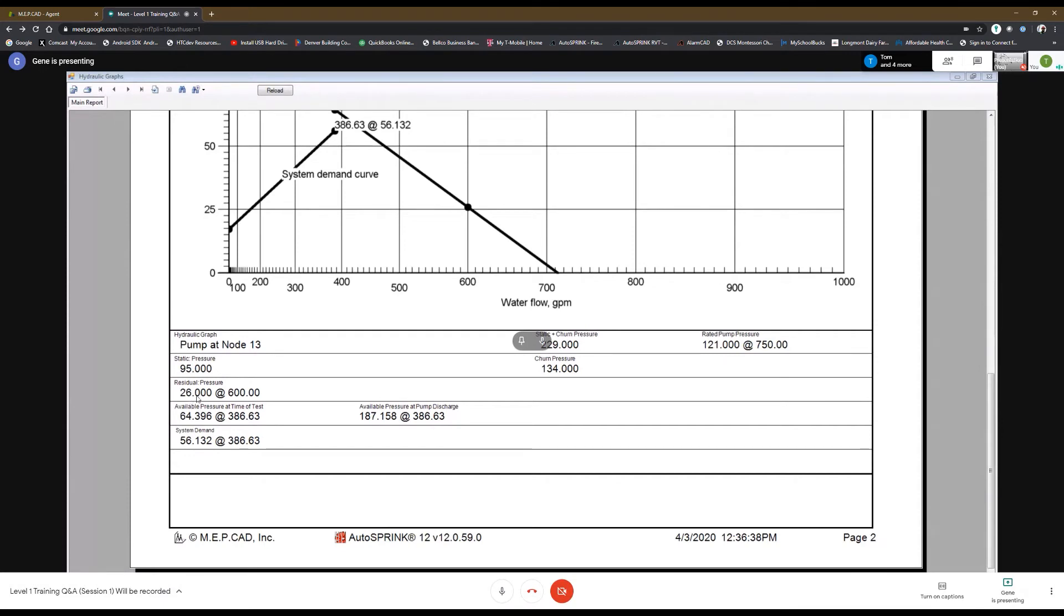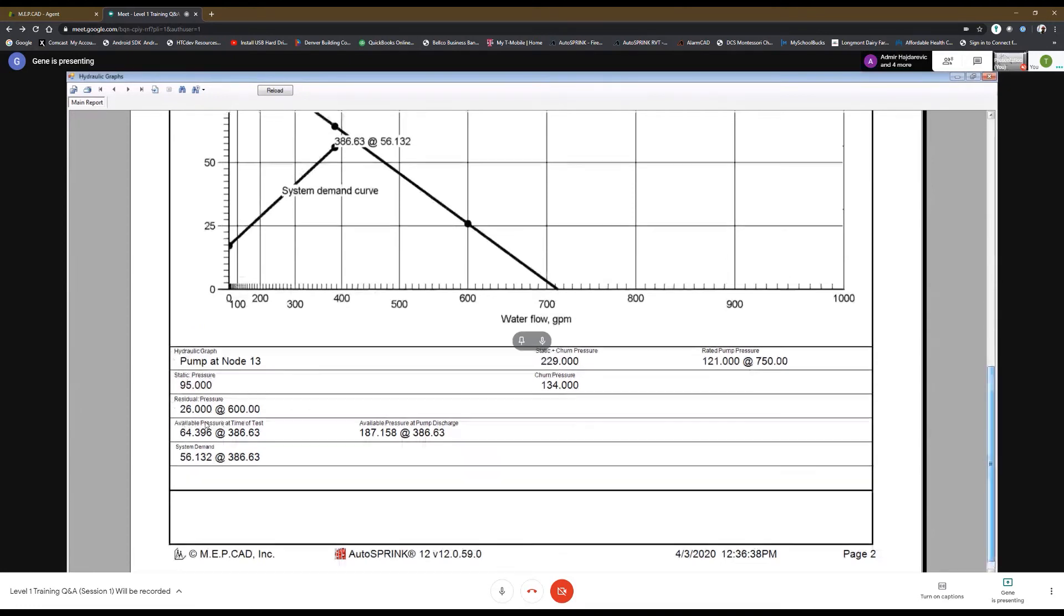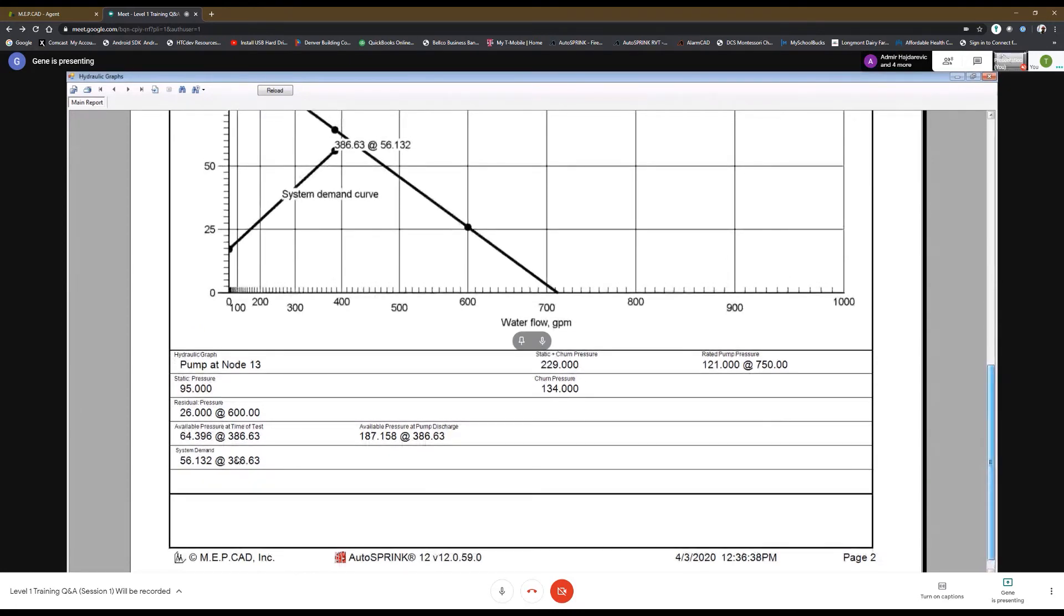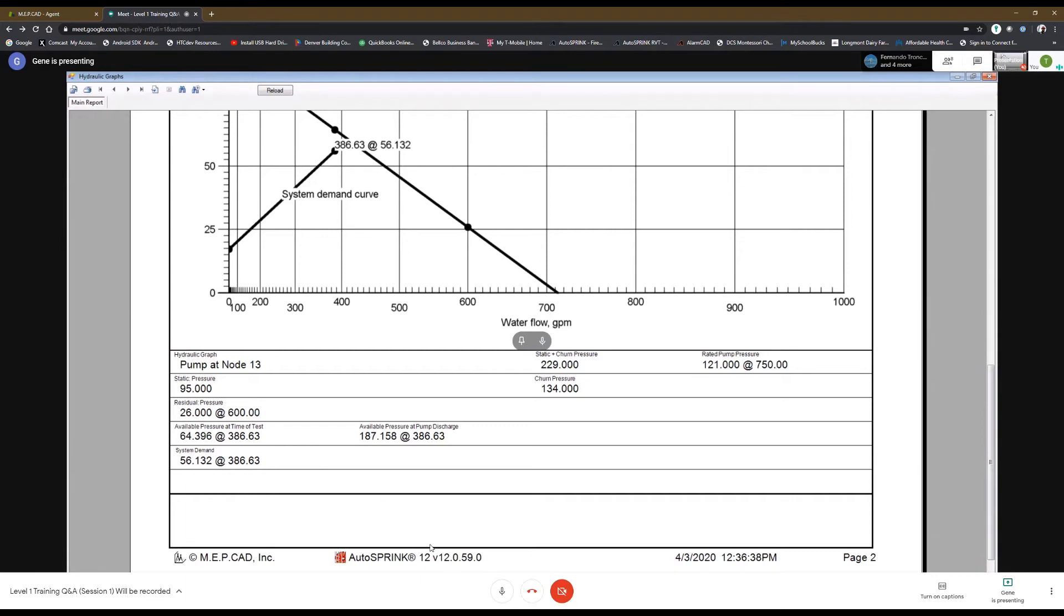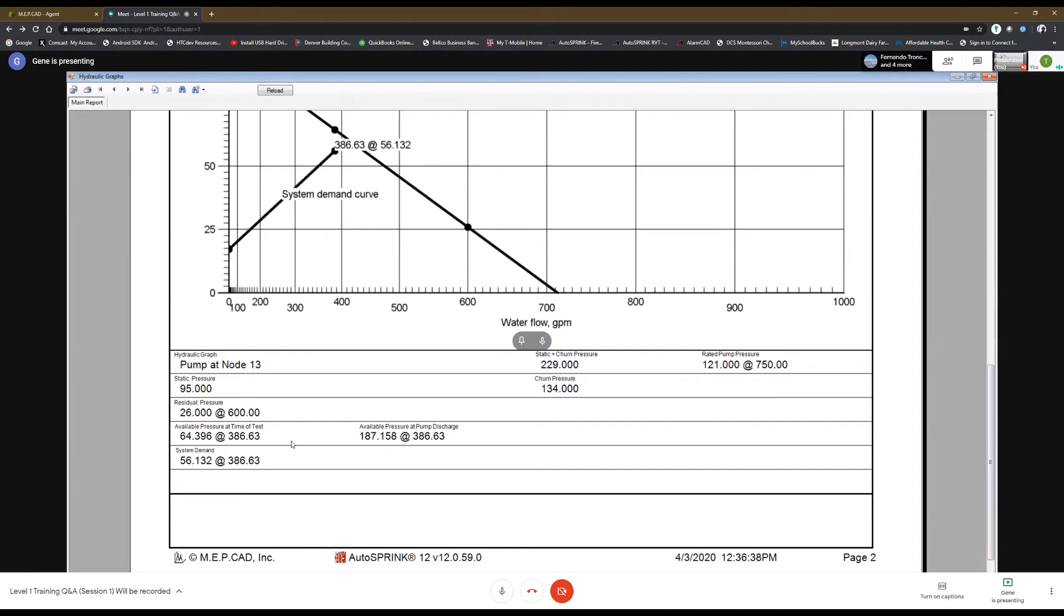Yes, sir. So, there's a bit of a safety factor at the fire pump here. So, the program is basically saying that you've got 64 PSI available at the fire pump, and your system requires 56 PSI at the fire pump. This is an older version of Autosprink. This is, you're on 12. Yeah, it's 12. I believe in 2019, and I could be wrong, but I feel like in 2019, the program populates the total demand as well as the demand at this point. So, in the version that you're on, the program is only populating the demand at this point.